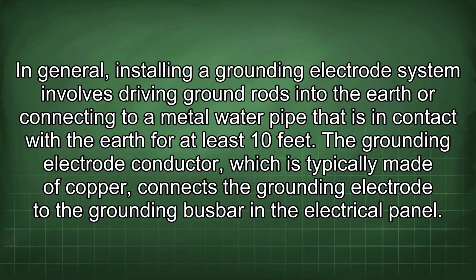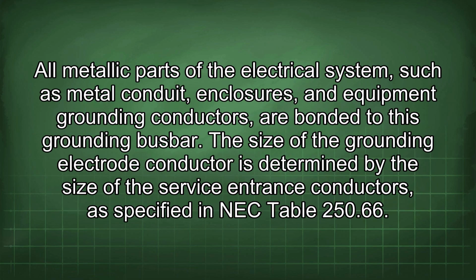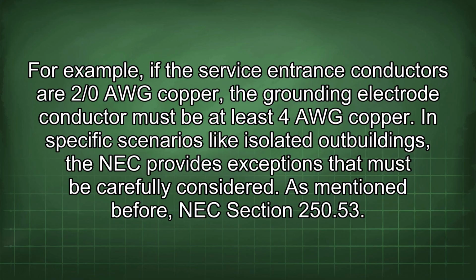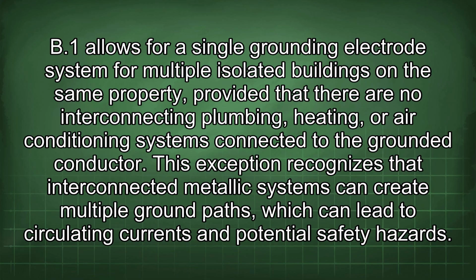The grounding electrode conductor, which is typically made of copper, connects the grounding electrode to the grounding busbar in the electrical panel. All metallic parts of the electrical system, such as metal conduit, enclosures, and equipment grounding conductors, are bonded to this grounding busbar. The size of the grounding electrode conductor is determined by the size of the service entrance conductors, as specified in NEC Table 250.66. For example, if the service entrance conductors are 2/0 AWG copper, the grounding electrode conductor must be at least 4 AWG copper. In specific scenarios like isolated outbuildings, the NEC provides exceptions that must be carefully considered. As mentioned before, NEC Section 250.53(B)(1) allows for a single grounding electrode system for multiple isolated buildings on the same property, provided that there are no interconnecting plumbing, heating, or air conditioning systems connected to the grounded conductor.